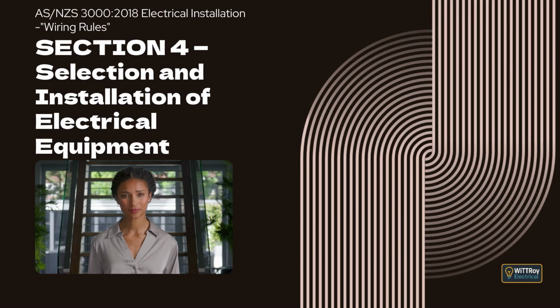Clause 4.2.2.3 Protection from high temperatures. This clause explains how fixed electrical equipment that can reach high temperatures must be managed so it does not create a fire risk. It explains that where surface temperatures could ignite nearby materials, the equipment must be mounted on or within materials that can tolerate the heat and do not easily conduct heat, or be screened from combustible building elements using suitable heat-resistant materials, or be mounted far enough away so heat does not cause damage, with supports that limit heat transfer and allow safe cooling.